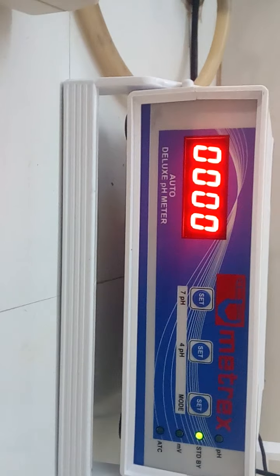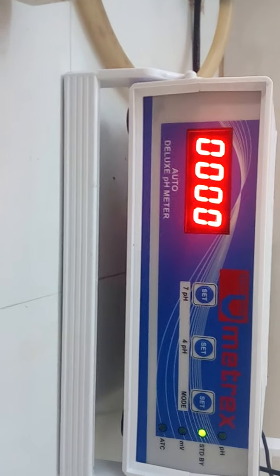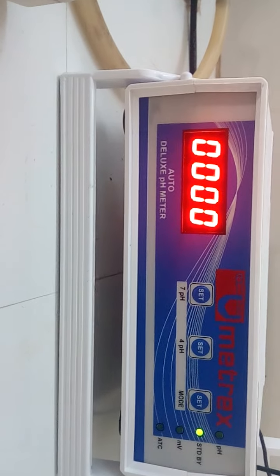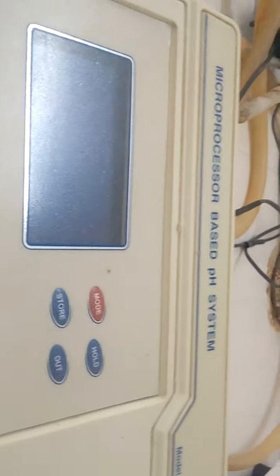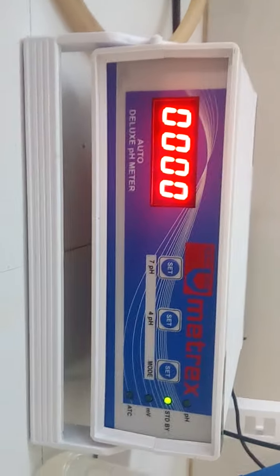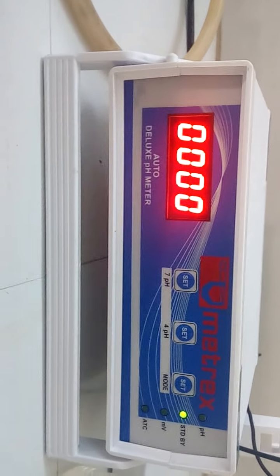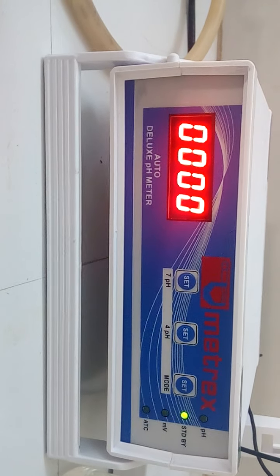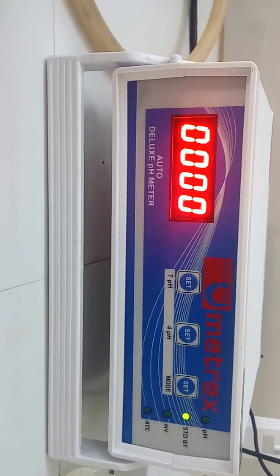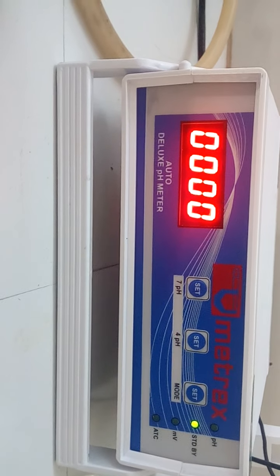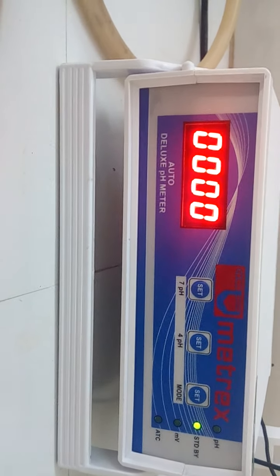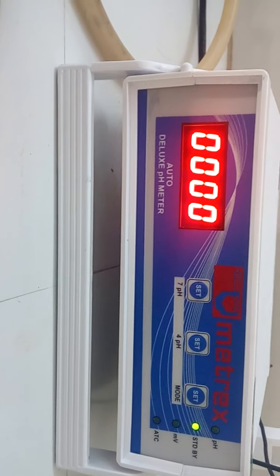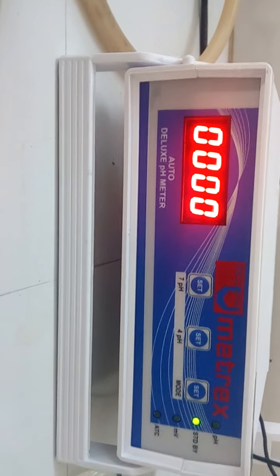This is the pH meter. Many brands are available in the market. This is a brand of Metrex and this is a brand of Asico. A pH meter is a simple device to measure the acidity or alkalinity of a solution. A pH meter acts as a voltmeter that measures the electrical potential between the pH electrode and the reference electrode and displays the result.